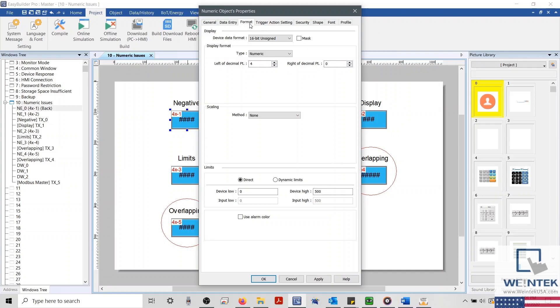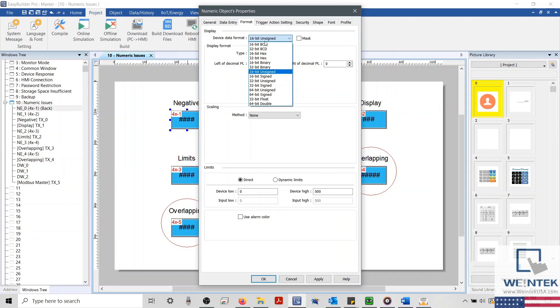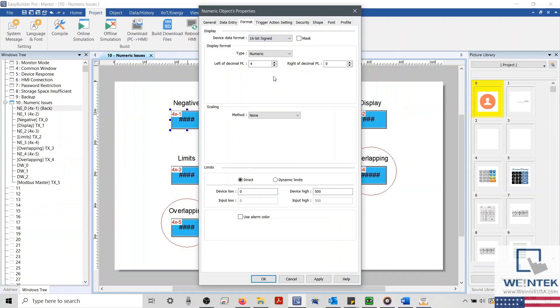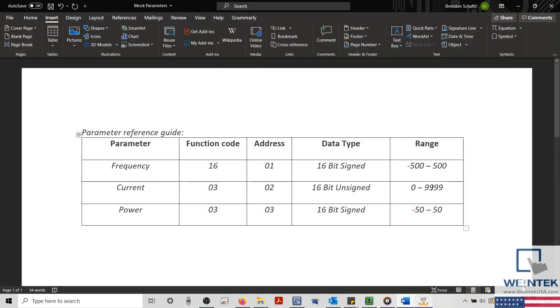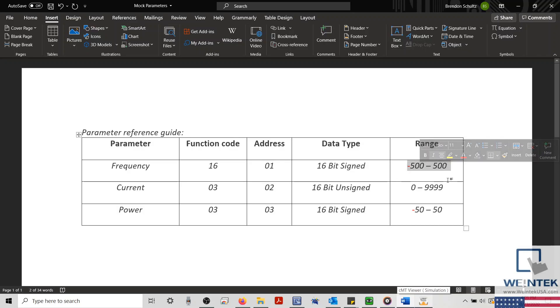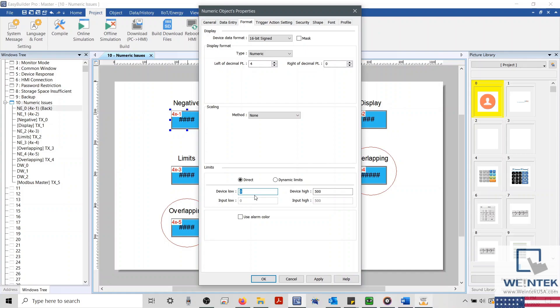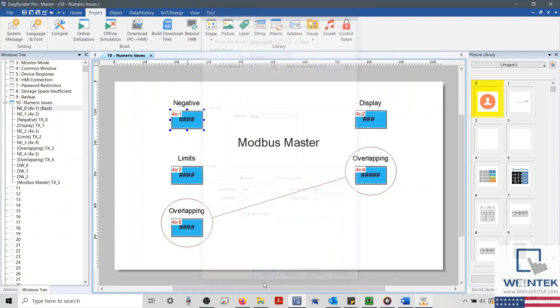And within our Format tab, I'll begin by checking the data format to make sure that our object can support negative values. We can see here that our data format is set to 16-bit unsigned. So let's change this to a signed format. And now we'll need to configure our limits. Checking my mock parameter guide, I can see that my limits should be configured from negative 500 to positive 500. So I'll change this here. So the issue there was that the data type and limits were incorrectly configured within the Format tab. This prevented the object from properly displaying the value received.